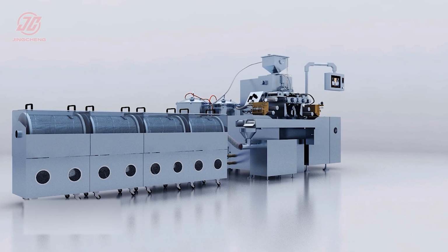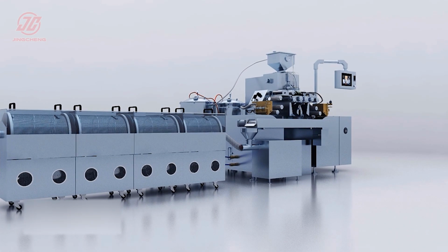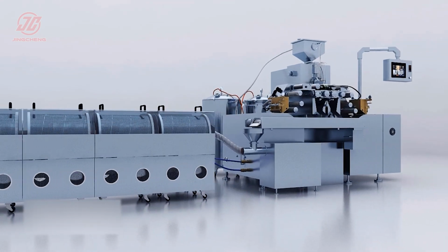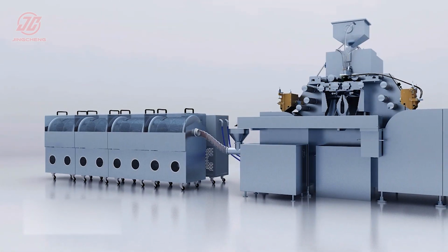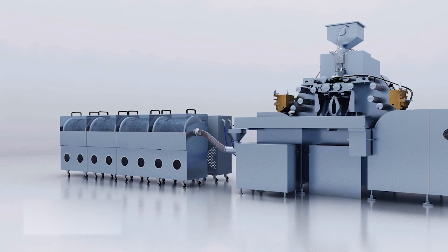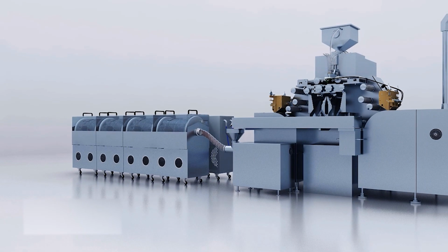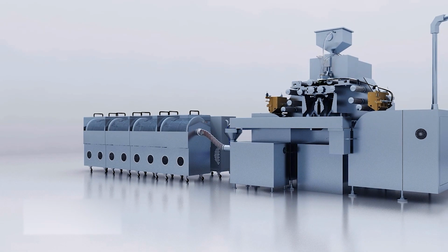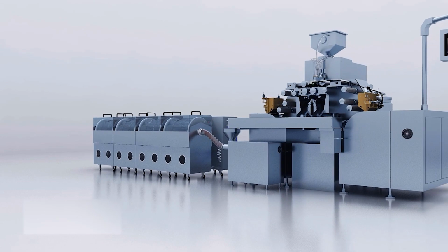4. After all the equipment is in place, connect all area sockets and connectors in accordance with the wiring connection diagram and confirm all the wiring is correct. Only after confirming OK, turn on the forward power supply for a power check and trial run.